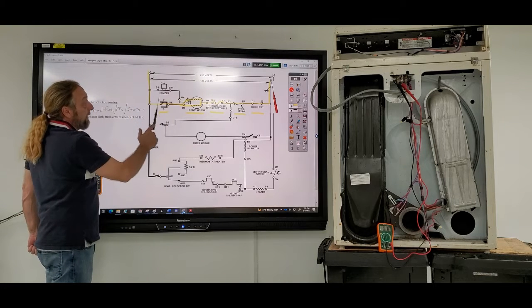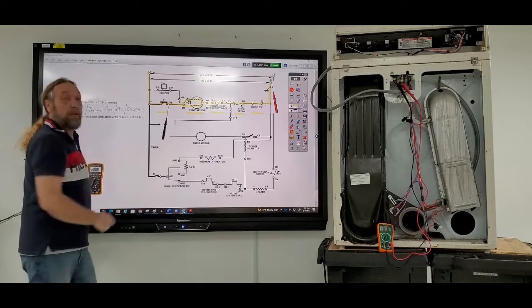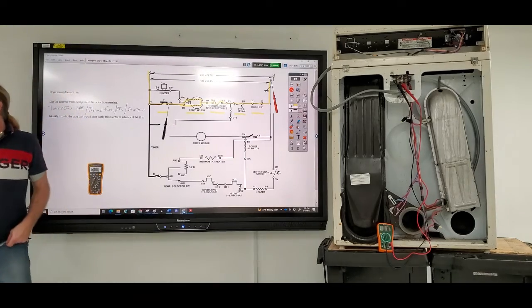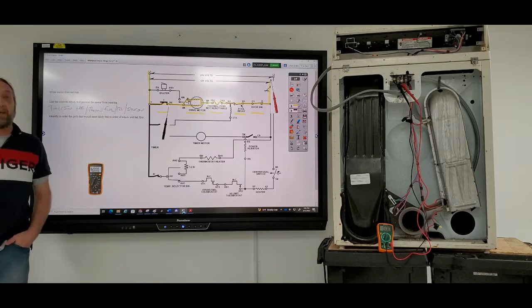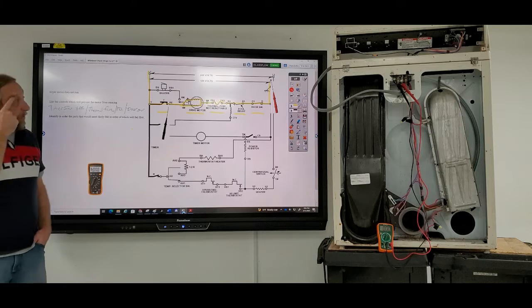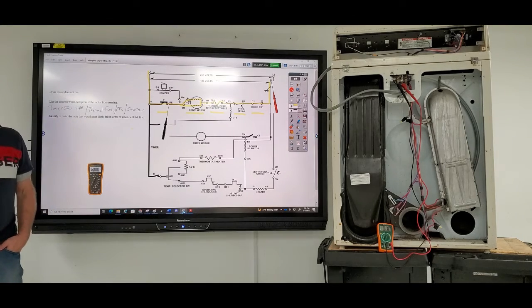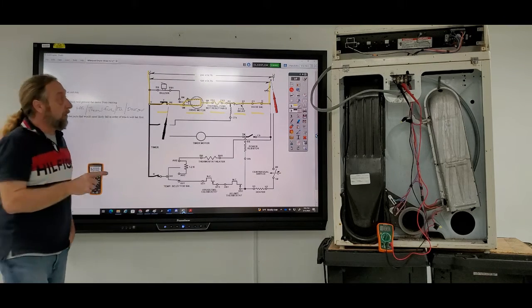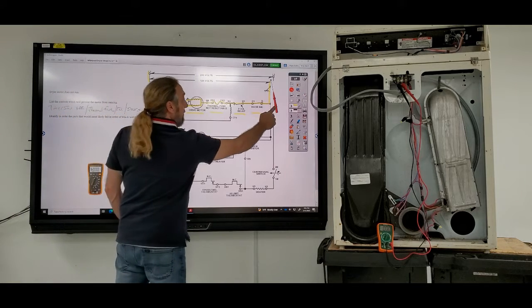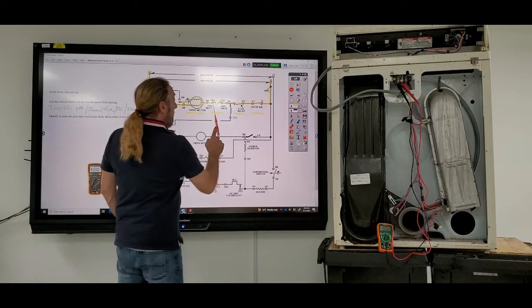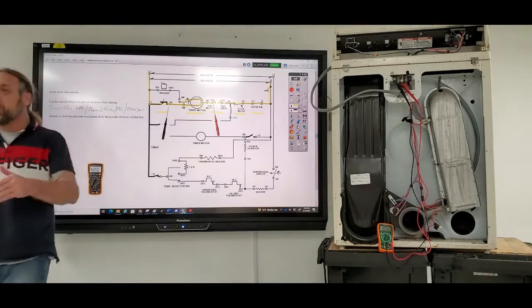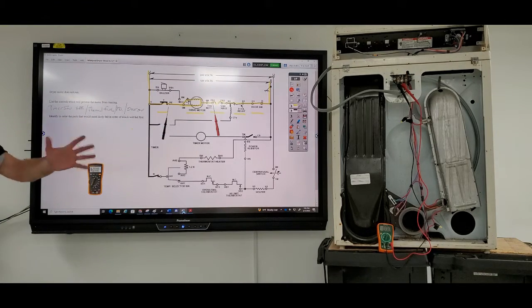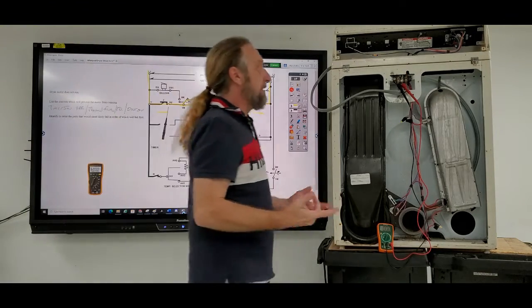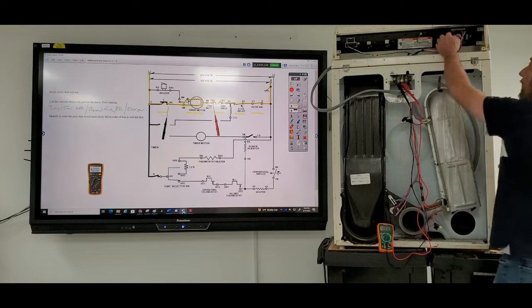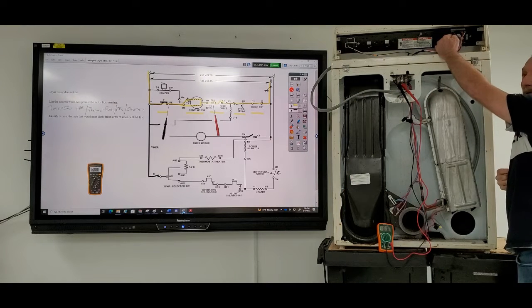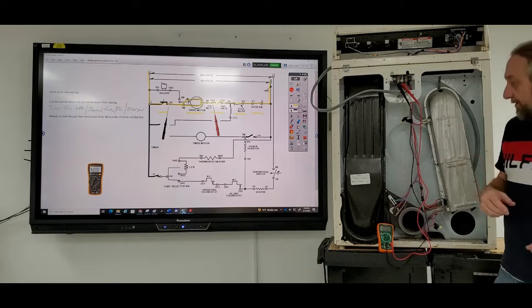So I can move my meter lead here to RE. Now on the other side of the motor, what's the next closest point we could get to? The thermal fuse — but where specifically? FS1, right here. Very good. That's as close to the motor as I can get from back here. In this case it's not RE, it's the blue wire on the timer — the colors aren't the same on this unit.